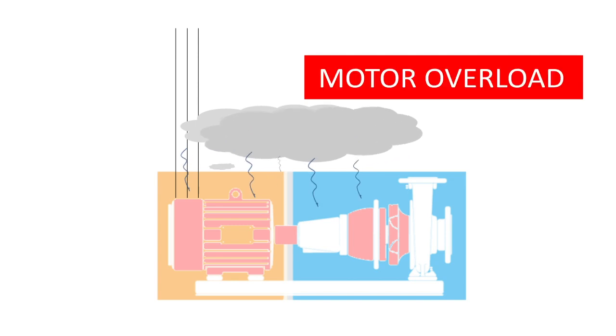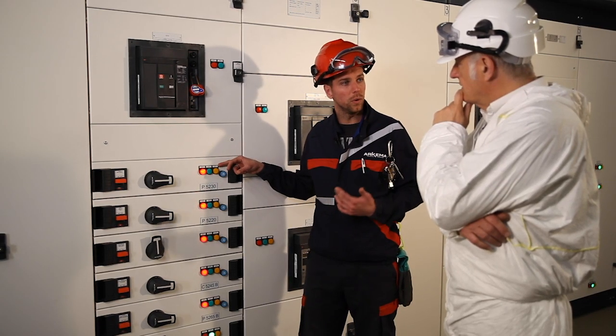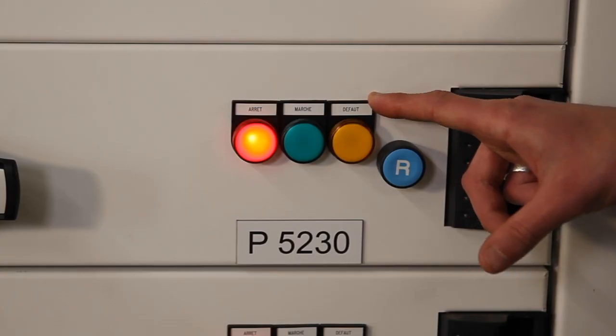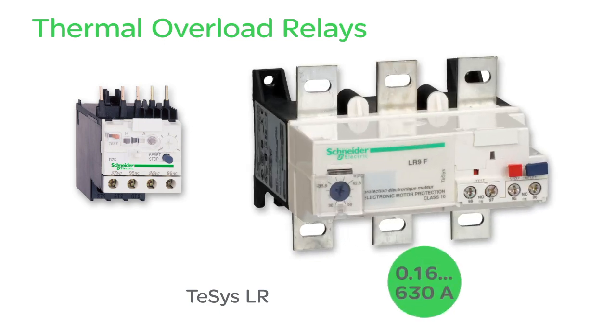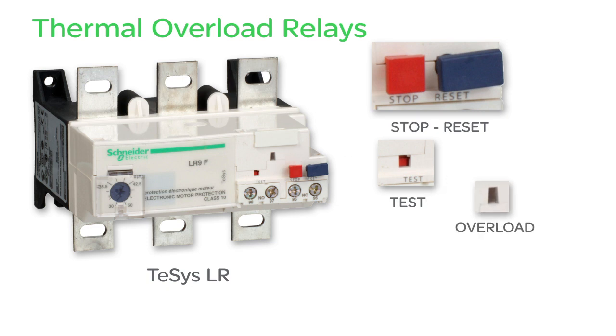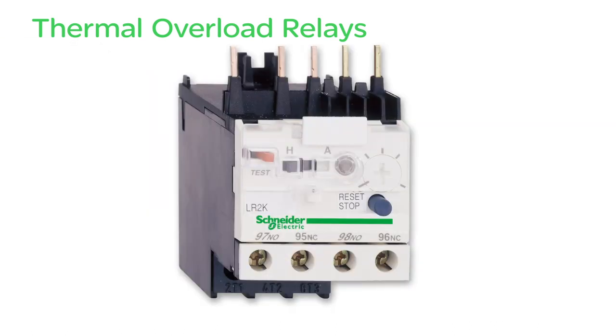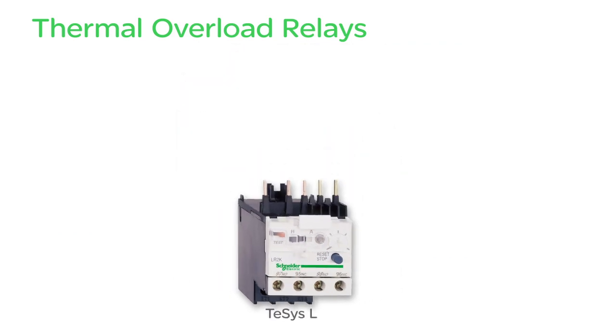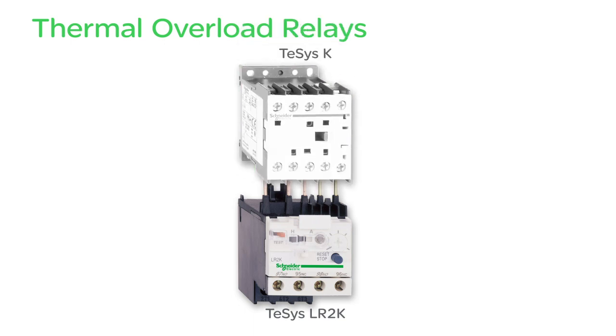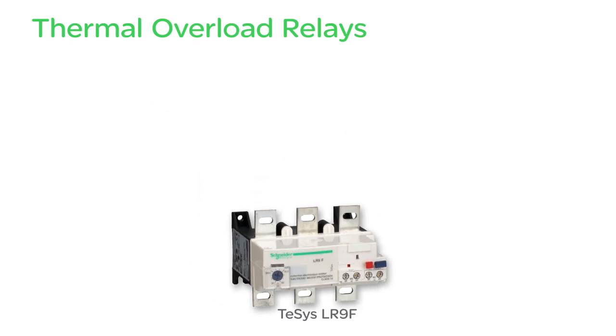We also have to ensure thermal protection against overloads. We've installed a thermal relay under the contactor, which can cut off the power supply to the contactor coil. It is relayed by a malfunction signal on the front panel and on the supervision screen, so we can easily reset it when the malfunction has been resolved. TeSys LR thermal relays cover currents from 0.16 to 630 amperes. They have stop and reset buttons, a test button, an overload indicator, and terminals for controlling a contactor coil and external signaling. The relay must be adapted to the contactor: TeSys LR2K relay for a TeSys K contactor, LR8 or LR9D for a TeSys D contactor, and LR9F for a TeSys F contactor.